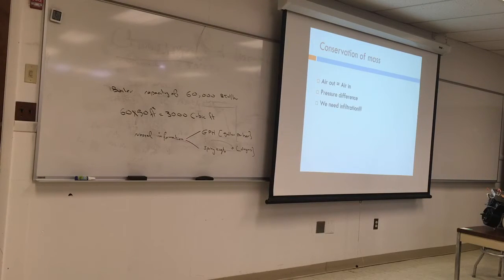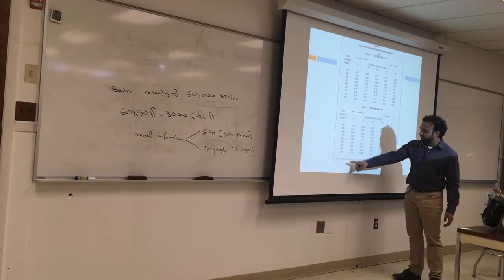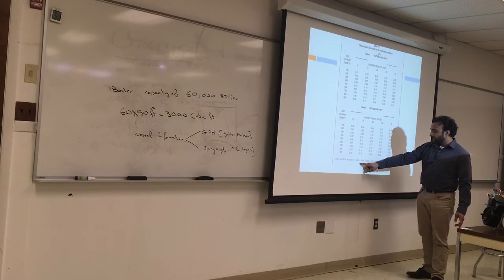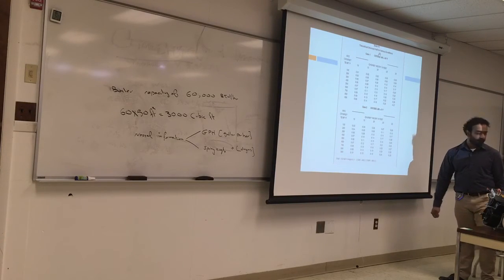So that math on the bottom, is that how you figure it out? Yeah, if you have a different chimney, you can measure the chimney. You have the draft, a constant for the air, the height of the chimney, and the temperature of the heat coming out of the boiler, plus 460, again, it's a conversion, temperature plus 460. That will give you the amount of draft you're supposed to have on the stack. Otherwise, you have to do some modification.